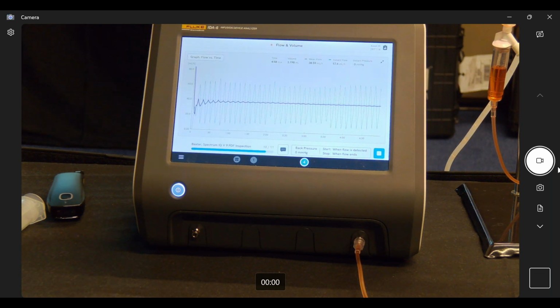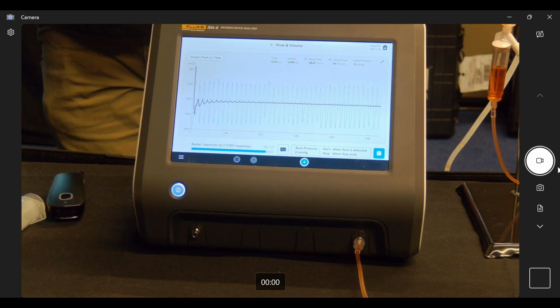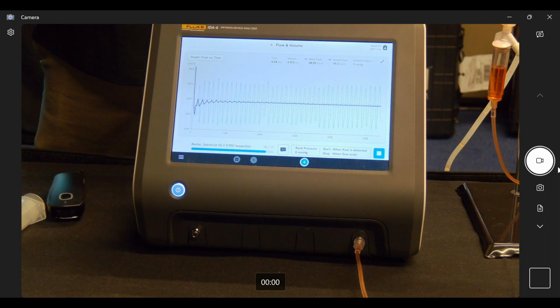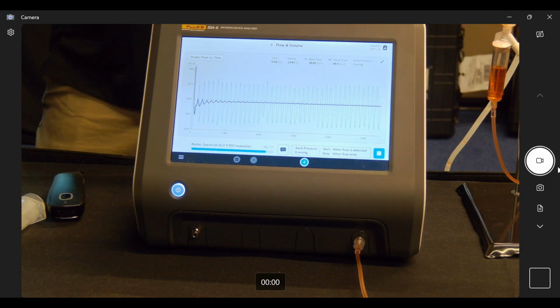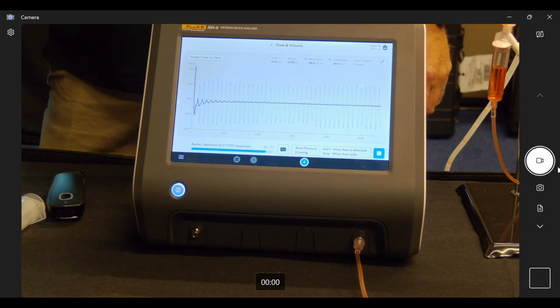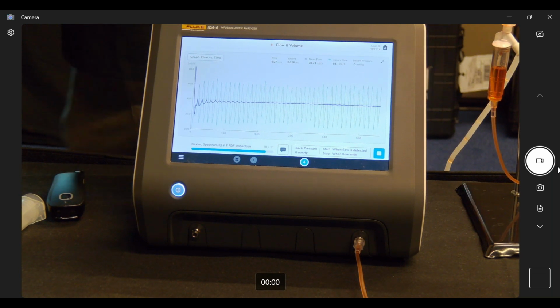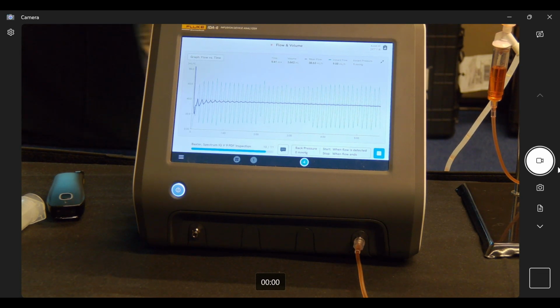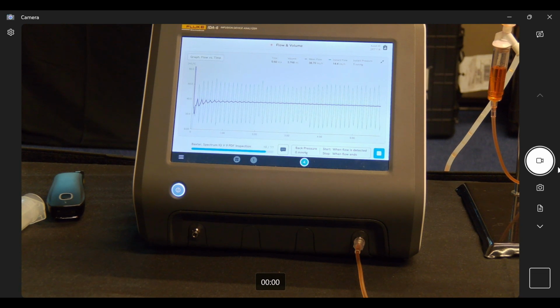So do I have any clinical engineers in here who are not biomeds, but actual clinical engineers? There are some really neat things that you can do with this when you're going into a clinical application. Because when you start talking about administering these drugs to a patient, what is the spacing that you have around your ICU beds? Do you have 14 feet on all sides? Nobody does. So if you have to cram 8 IV pumps in there, can you actually do it? How long are your PICC lines? Are you able to push through a 16 gauge needle? So if you have to extend your PICC line so you have the distance for your IV pump, and you have to run it through an 18 gauge PICC line, what's the head pressure and what's that doing to the volume infusion with your patient? Things I didn't talk about, but you'll also notice on the screen, if I needed to, I could introduce back pressure. So great question. I told you we should only push distilled water. But if we wanted to simulate pushing a more viscous solution, blood, or feeding different drugs, we can take the differential and enter it as a back pressure and put a back pressure against the pump pushing it in.